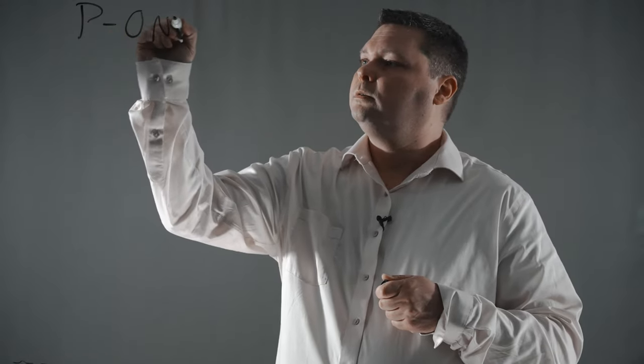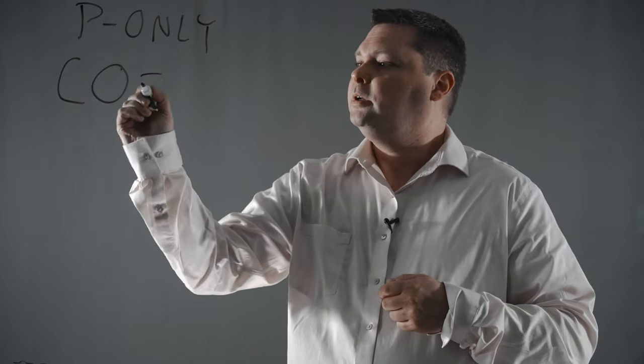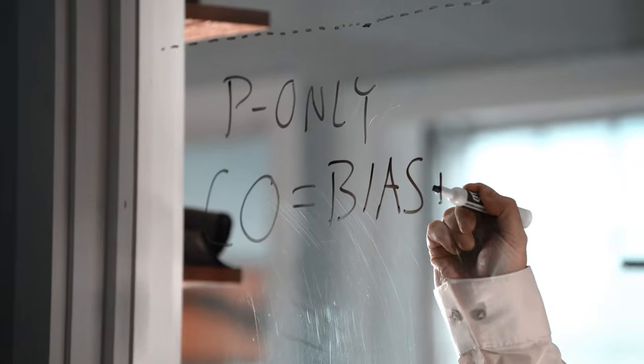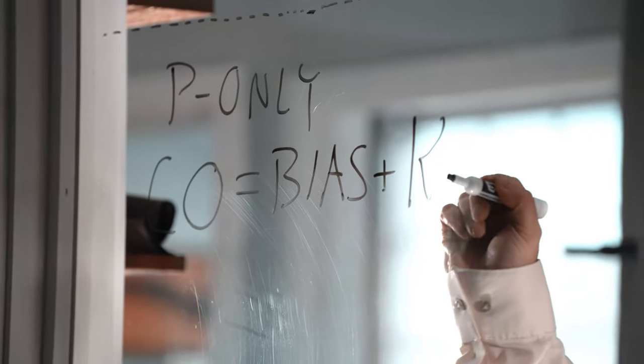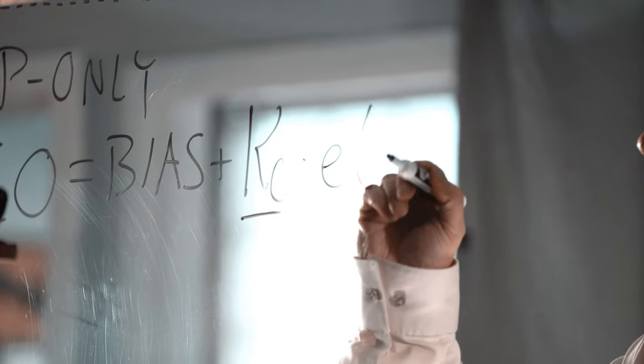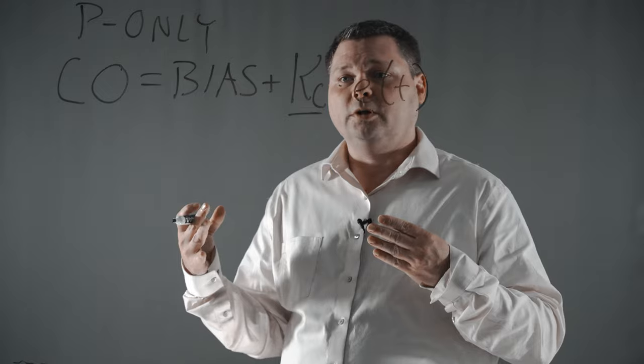So a P-only controller is the controller output is equal to some bias value, which is a starting value of your controller, plus your controller gain value, in this case it's Kc, times whatever your error is. This is the equation for a P-only controller.